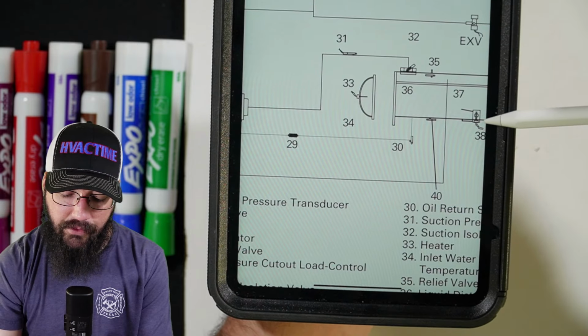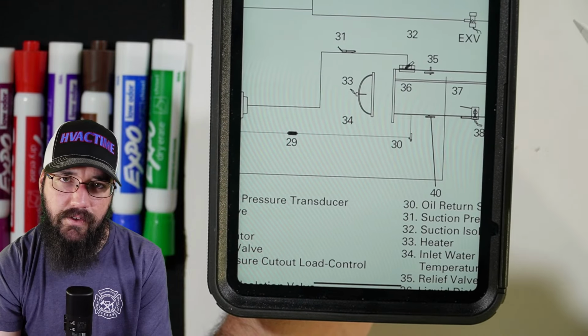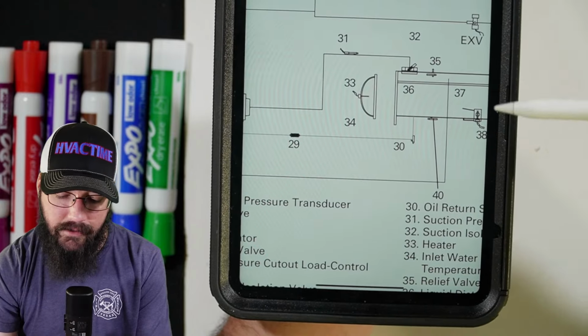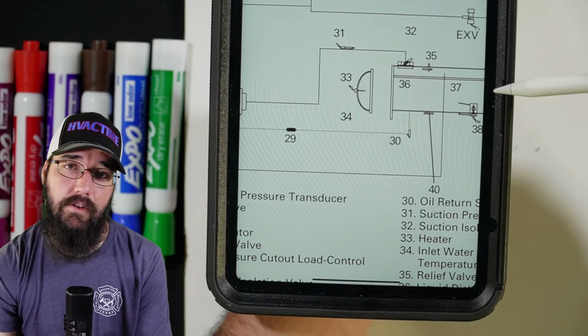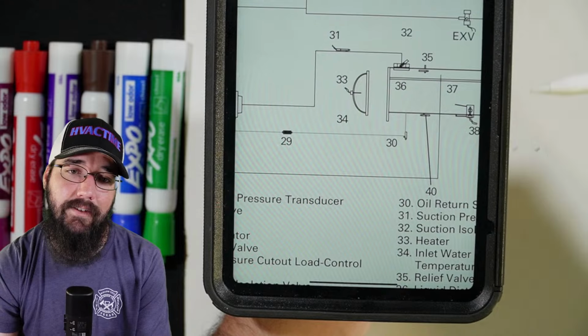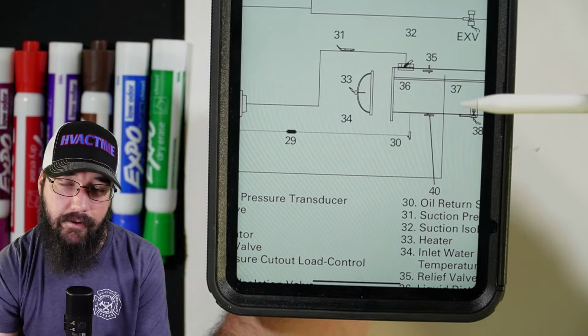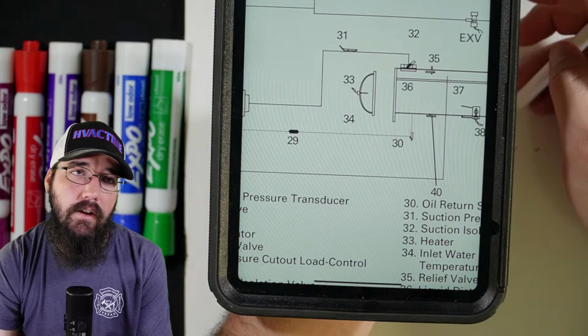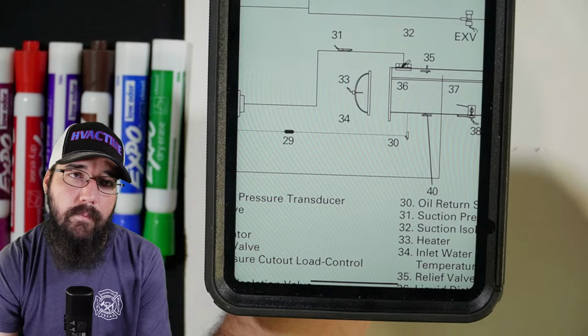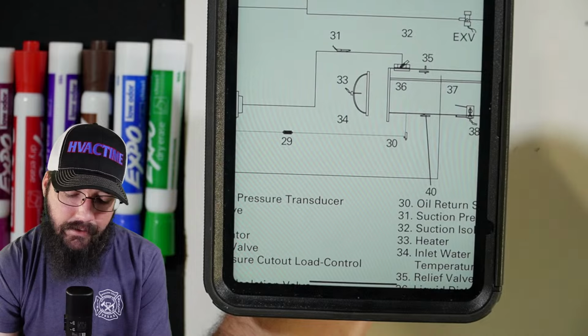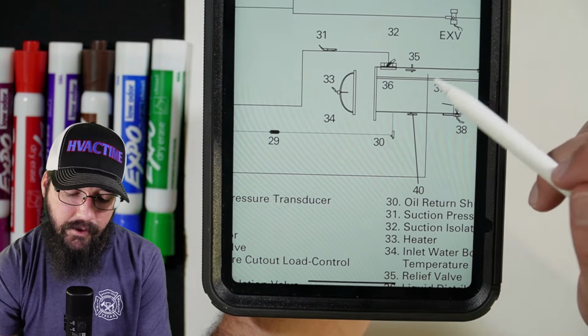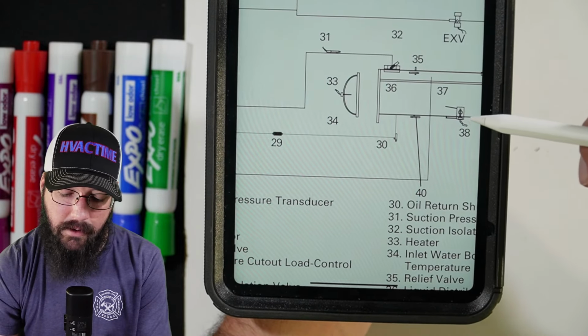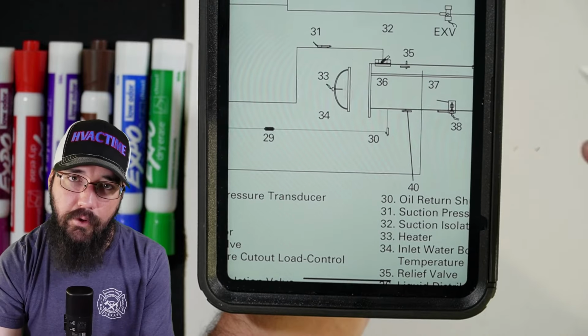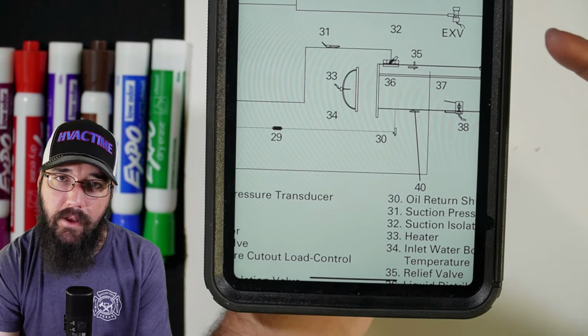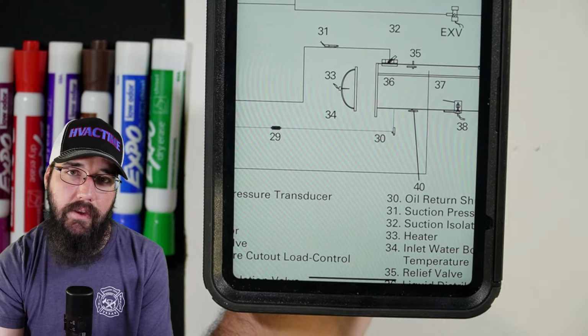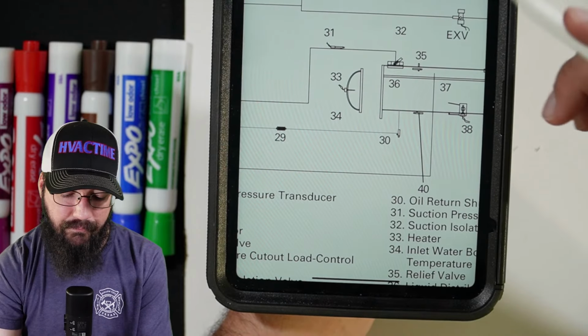I think these machines did use, or at least some of them did use, the original level sensor design. The original level sensor with an actual float magnet in there does get affected by the oil. That oil will cause it to float up, and it will read a higher level than is actually there. In that case, that'll actually end up starving your evaporator. In order to fix that, we've got to get the machine to feed enough liquid refrigerant in there to start trying to get some of that oil back out. That is one of the major problems that Trane has had with their original float designs, is that oil, as it begins to get foamed up as the evaporator is running, will cause a lot of issues with that level reading really high, which will cause your metering valve to pinch off, and it just won't control correctly.